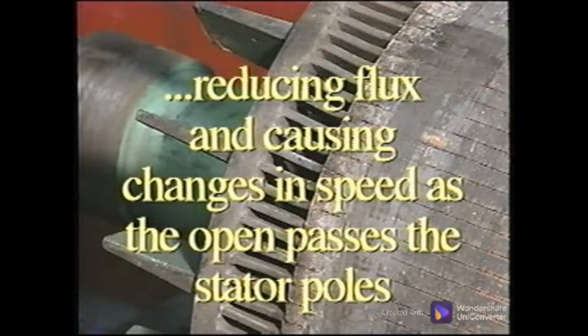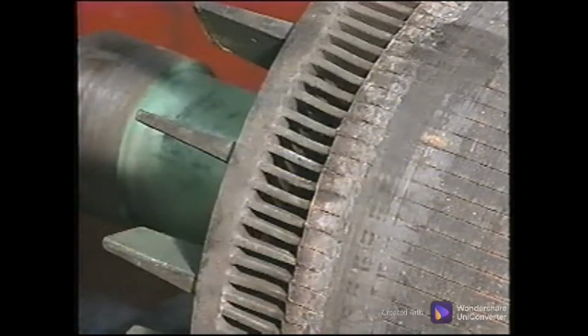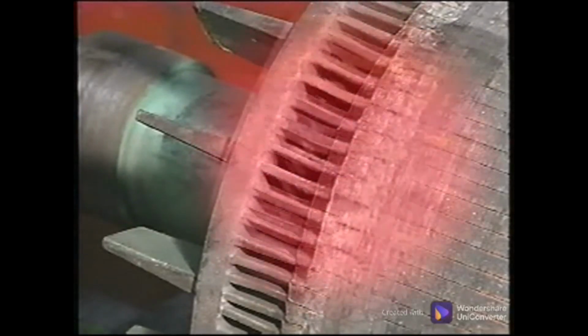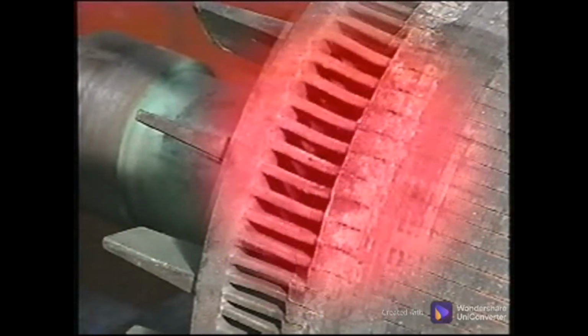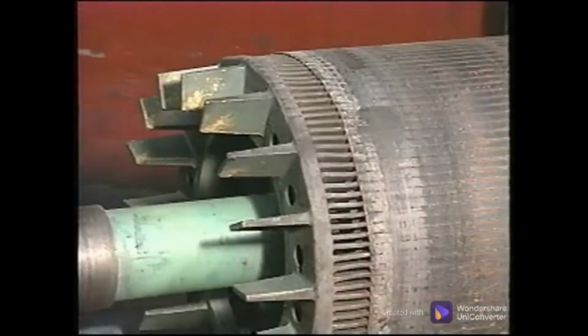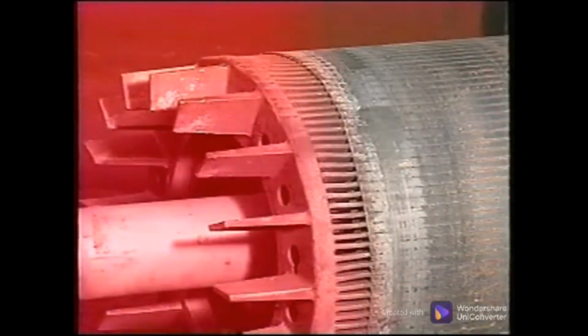The reduced flux causes changes in rotor speed as the open area passes the stator poles. The open also generates heat. The excessive heat causes the rotor to expand at that location, resulting in an unbalanced condition. The heat also causes the rotor to grow axially, putting additional force on the bearings, accelerating their degradation.